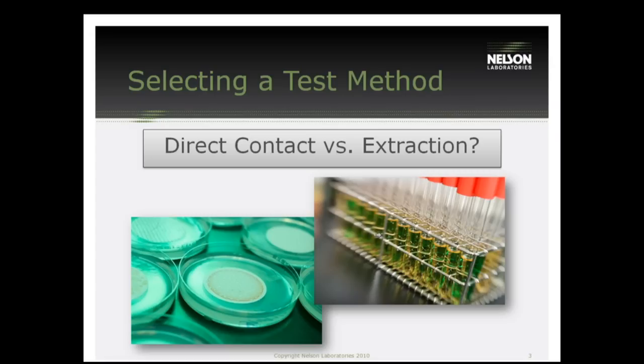How to choose what test to run depends on the device you have. If you have a pure skin-contacting device, you want to use the direct contact version, because that mimics skin contact. It's less sensitive, so if you have something like Velcro with a lot of surface area, that helps. The extraction version is for devices that have body fluid contact — something that could be exchanging with the body — and is considered more sensitive. These are devices with wound contact, blood contact, really anything that's not skin-contacting. If there's a gray area, go with the extraction method, as it's considered worst case.